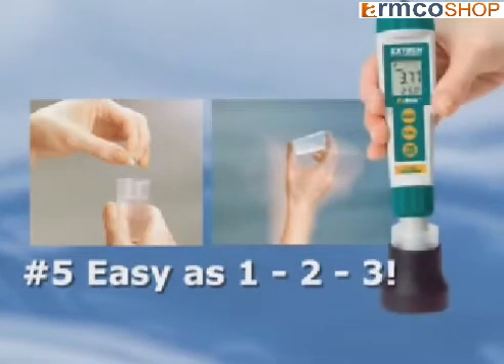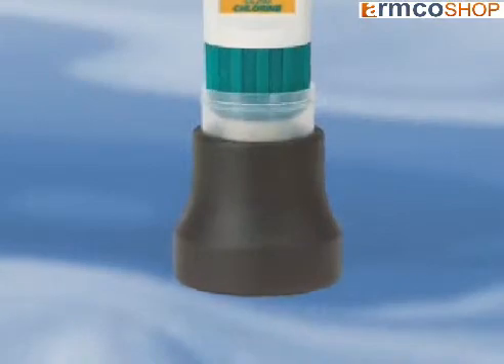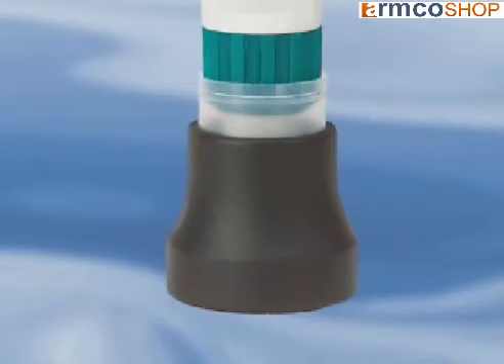Number 5. It uses a quick three-step procedure to take a reading. Drop one X-Tab reagent tablet into the 20 milliliter sample solution using the cup provided. Shake vigorously for a few seconds until it dissolves. Turn the EXTECH chlorine meter on and insert it into the cup. Once the reading stabilizes, the hold symbol will come on, displaying the measurement. An optional weighted base is recommended for hands-free operation while holding the meter and solution in place.